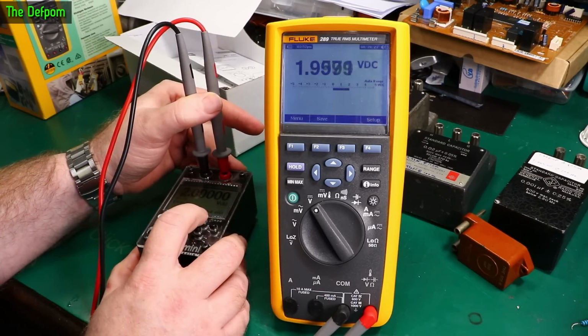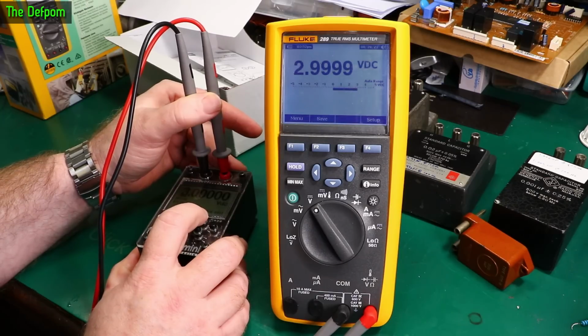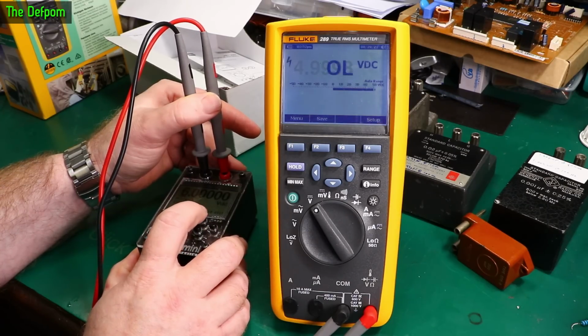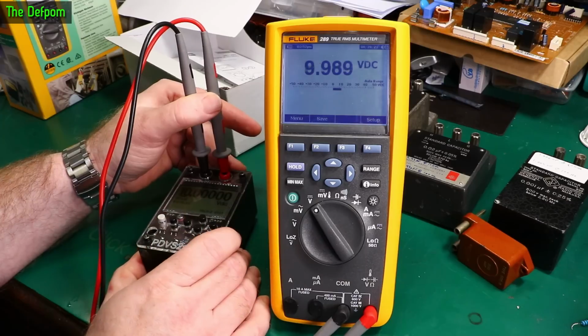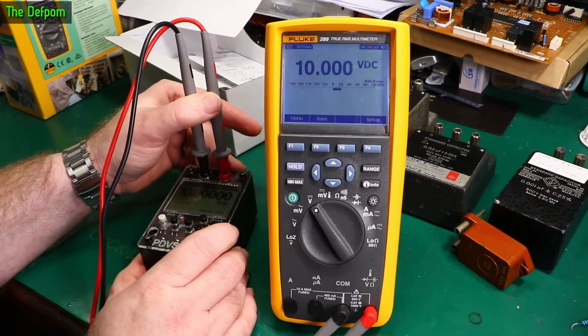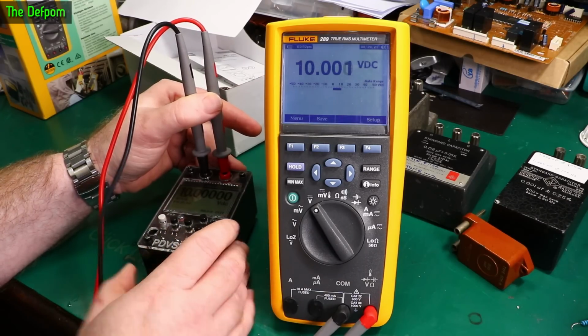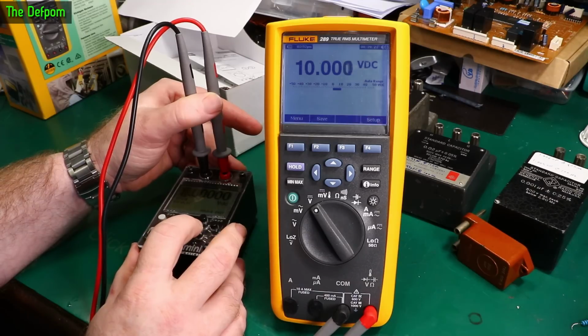If I can just turn it on. 2 volts. Yep, bang on. 3, 4, 5. Let me get 50,000 counts. So that should be right at the top end. 6 will change ranges. Yep, that's bang on. Up to 10 volts. Perfect. Only got 1 digit rounding there. But that's looking pretty good.